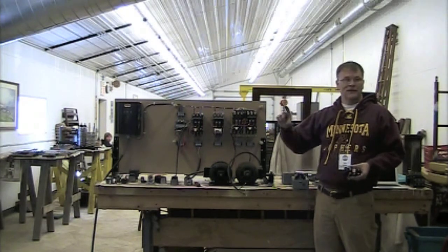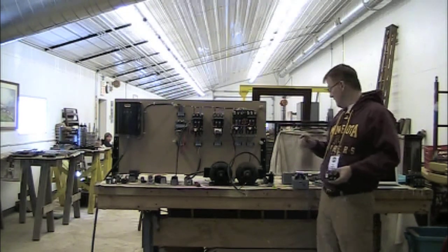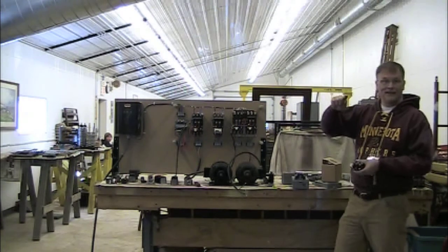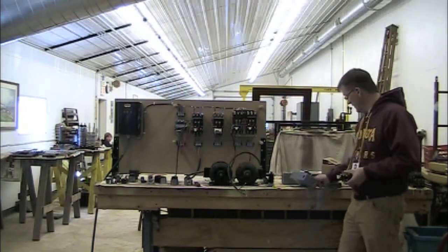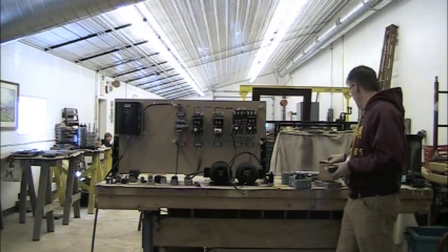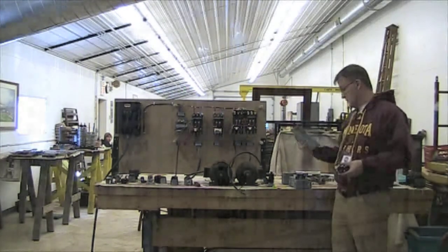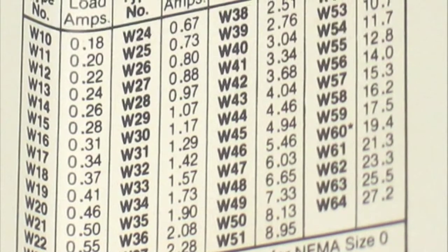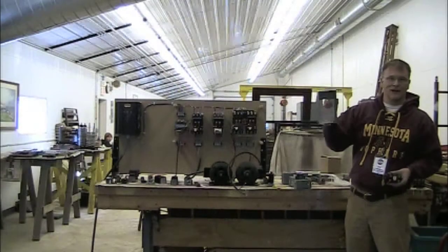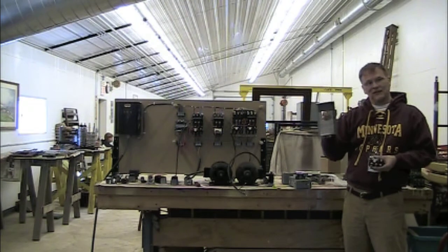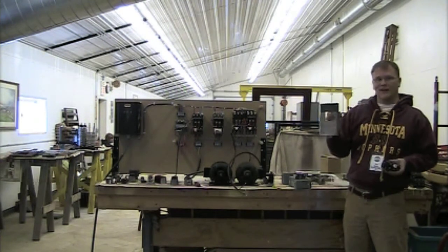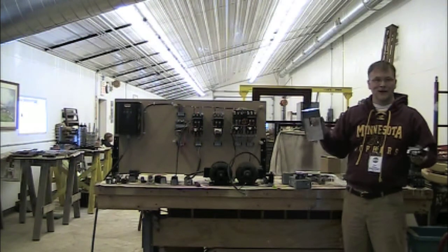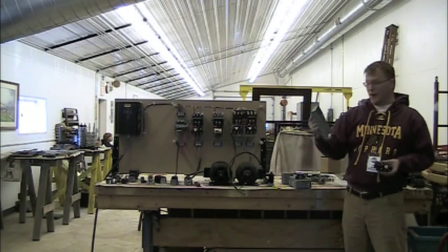There'll be another set of values specifically if it's in a NEMA 1 can. And those are usually, if you get one and everything's intact, the proper chart is going to be in the can. But if you're buying a starter and putting things together and changing one out in another can, you've got to get the right set. They're all really close, but if you look at them, they all differ by up to 10% or so, depending on the scenario.